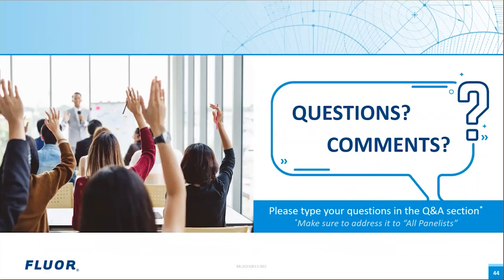It's quite a nice question again. Quite interested indeed. Yeah, of course, when we consider the treated or upgraded wastewater, and especially the permeate coming from the reverse osmosis, it's definitely a potential source. Indeed, as mentioned in the question, we can use it for cooling tower makeup, for process water, and for boiler feed makeup water. It depends, of course, on the pressure of the boiler system, because the qualities will differ.